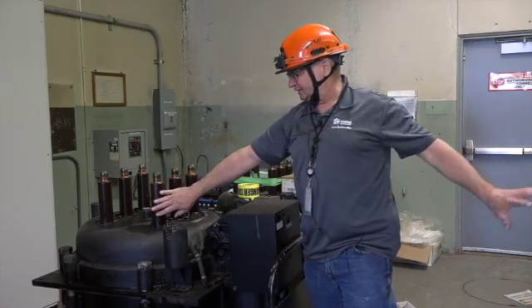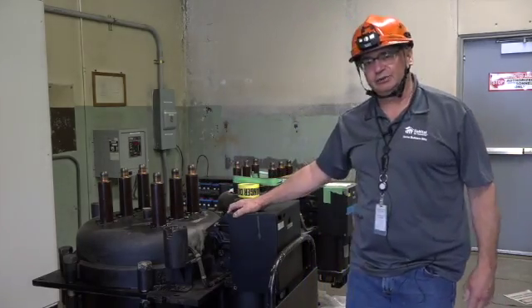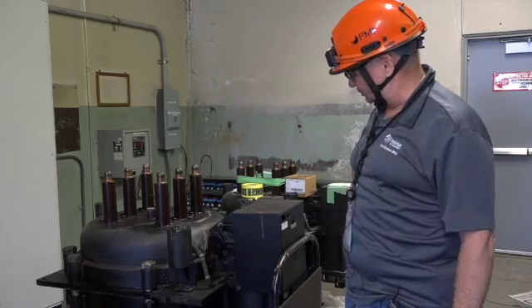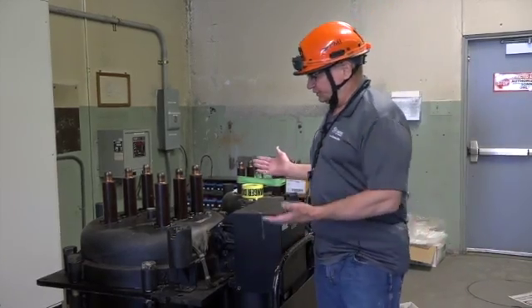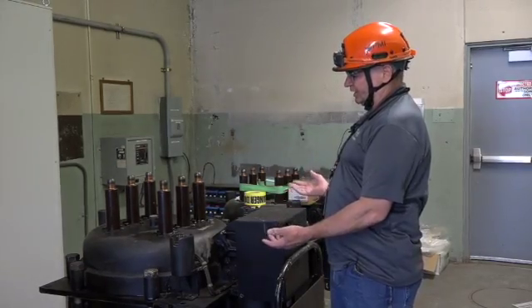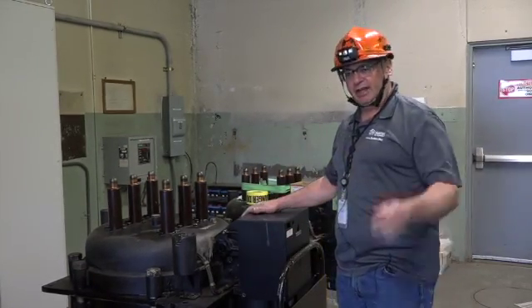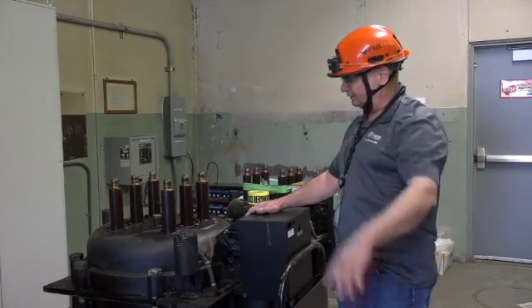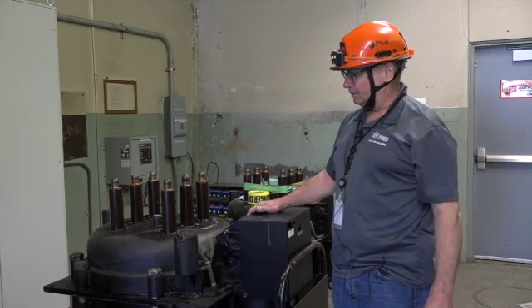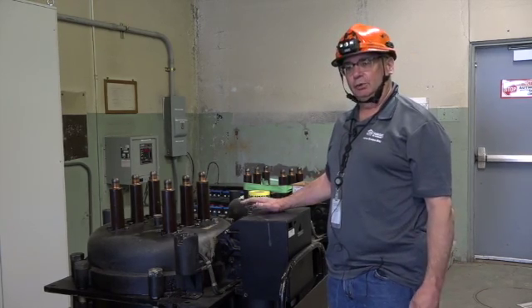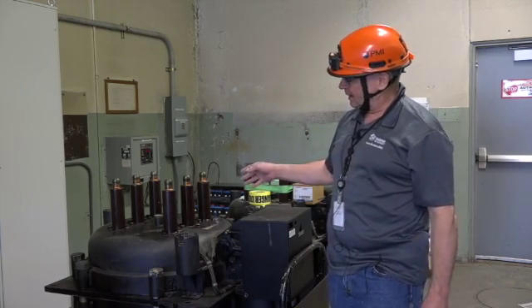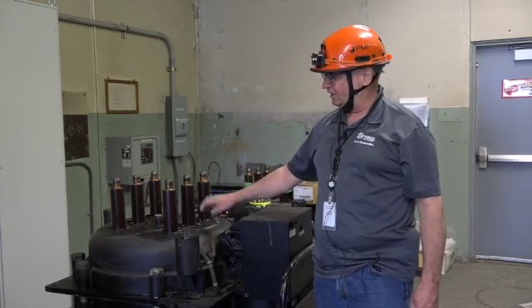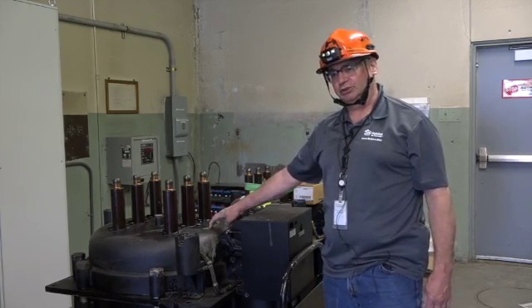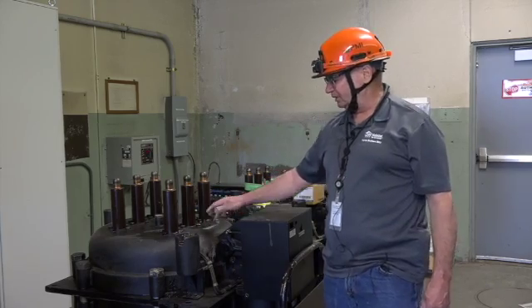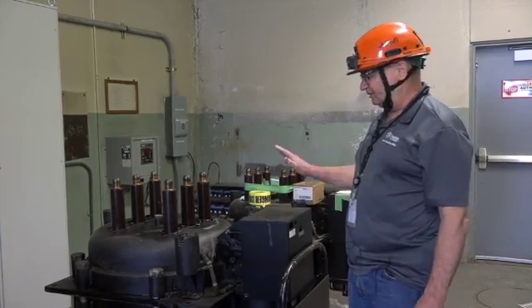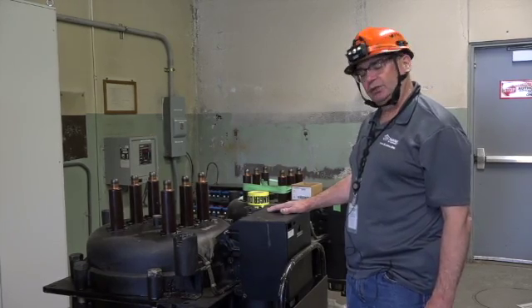On this substation here, 13,800 volts is what comes in, and that's considered medium voltage. So when these breakers are inside the substation gear, it opens and closes the circuit that goes out and feeds other lines. Shortly we'll be showing you some of the 115,000 volt, which is on the other side of the transformers, feeding the transformers, which then feed on the low side of the transformer, which is 13,800 volts, feeds these breakers. So this is just another level of electrical work that you may be interested in.